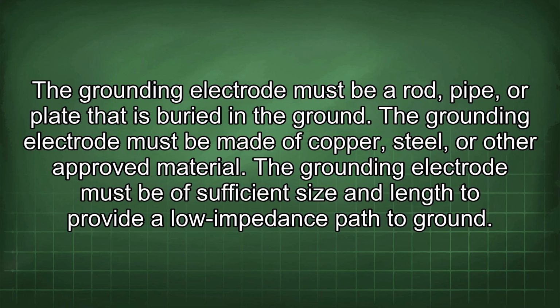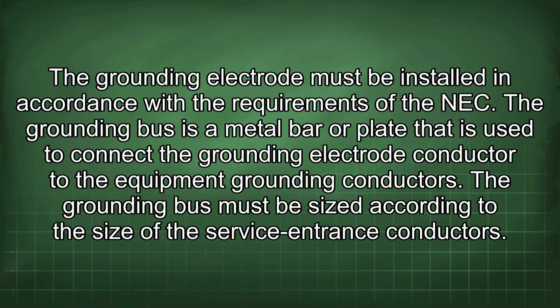The grounding electrode must be made of copper, steel, or other approved material. The grounding electrode must be of sufficient size and length to provide a low impedance path to ground. The grounding electrode must be installed in accordance with the requirements of the NEC. The grounding bus is a metal bar or plate that is used to connect the grounding electrode conductor to the equipment grounding conductors. The grounding bus must be sized according to the size of the service entrance conductors.